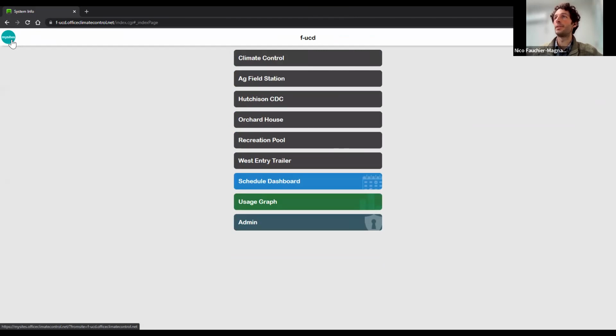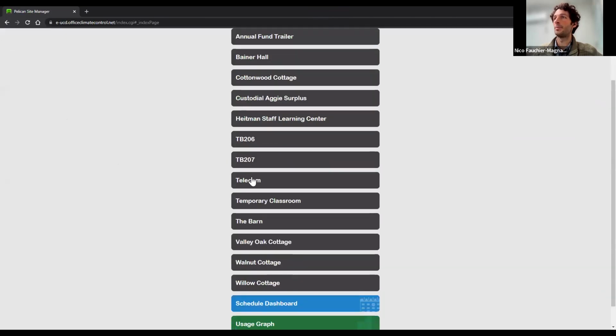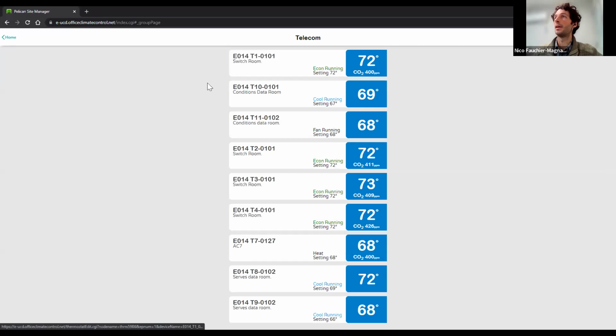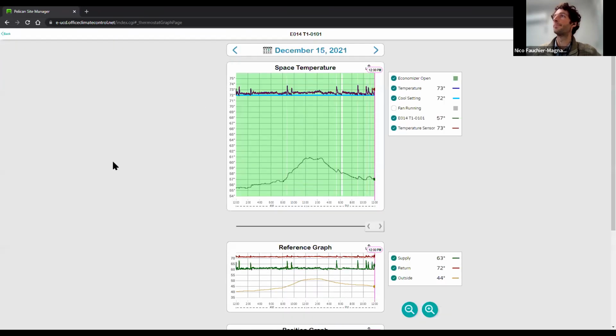The third thing I wanted to show you is the economizers that we've talked about a little bit. And for that, I'm going to take you to our telecom building. When we installed Swarm at this telecom building, it has a lot of IT loads in the building. You can see this unit is running its compressor. It doesn't have an economizer right now. But when we did put Swarm in place, we decided to add some economizers to the units. And I'm just going to show you what that did to our compressor runtime.